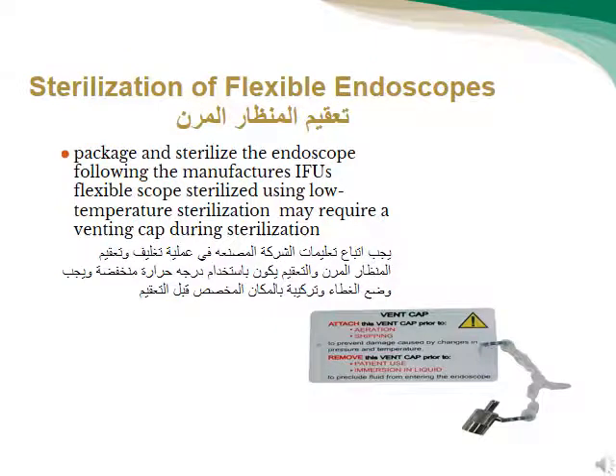Sterilization of flexible endoscopes: package and sterilize the endoscope following manufacturer IFUs. Flexible endoscopes are sterilized using low temperature sterilization and may require a venting cap during sterilization. تعقيم المناظر المرنة: يجب اتباع تعليمات الشركة المصنعة وقد يتطلب التعقيم درجة حرارة معينة.